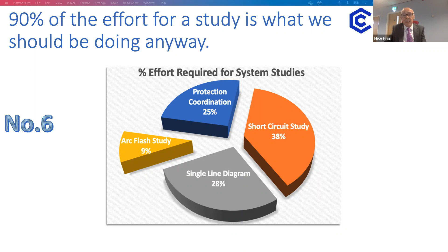A precursor to an arc flash study is to have a single line diagram. Who shouldn't have one of those? Next is a protection coordination study. And then finally, short circuit studies. Now, as you can see, the amount of effort that's required for the arc flash study is 9% of the total. Where do I get that from? Actually, it's from IEEE 1584, the previous iteration, which was the 2002 edition. It looked at those 4 categories and the amount of information you needed for each one. There's about 12 pages of the actual information you wanted for each one of those items. As it happened, the minority was the arc flash study.